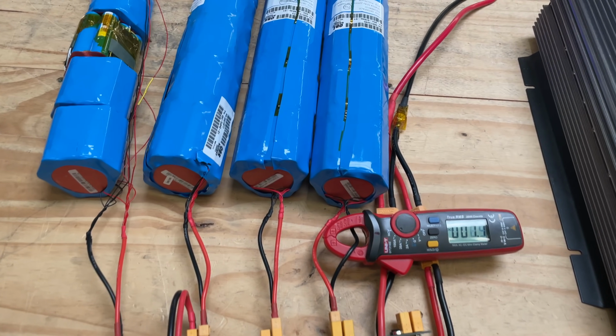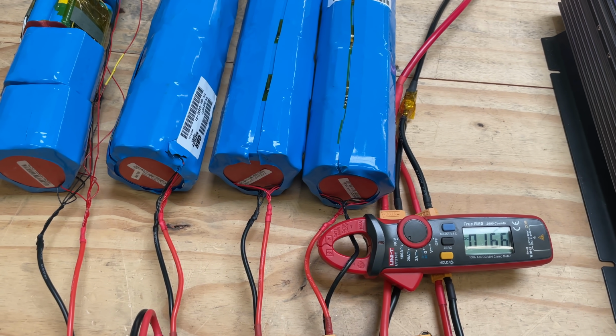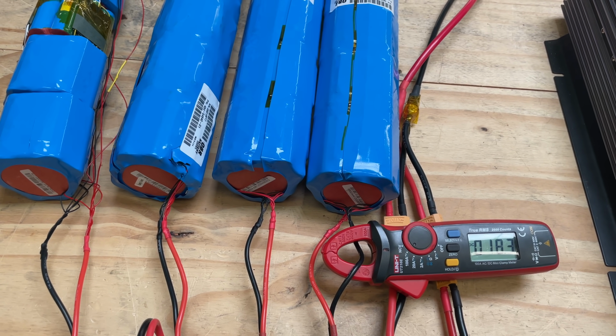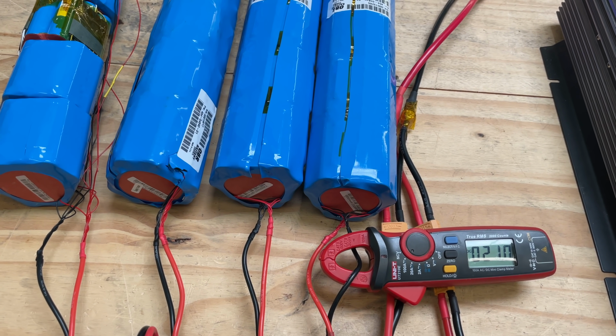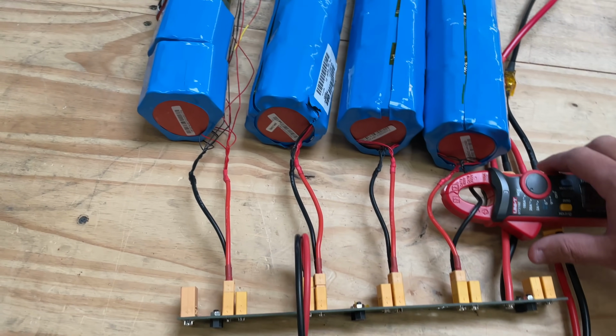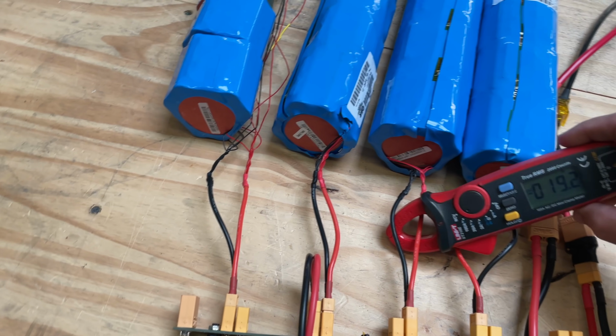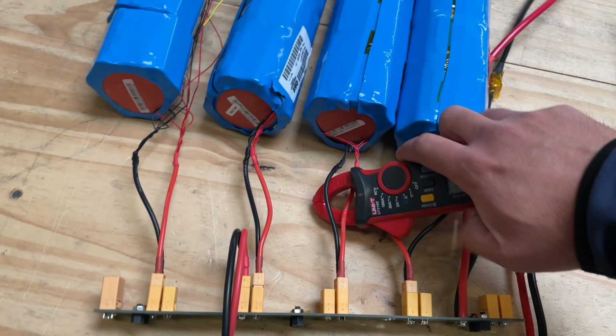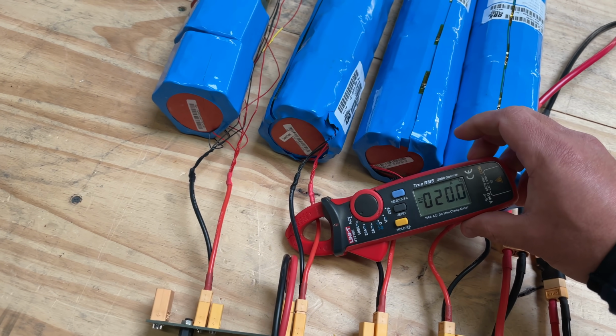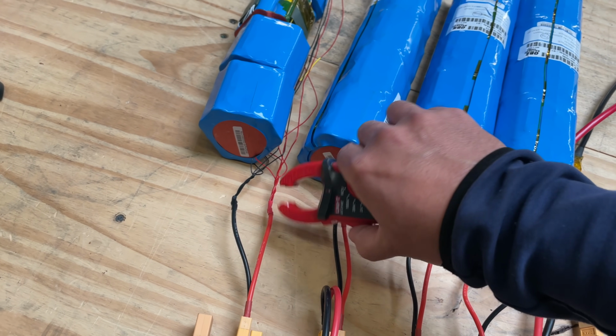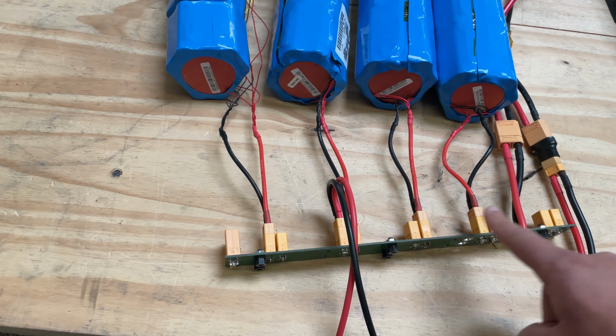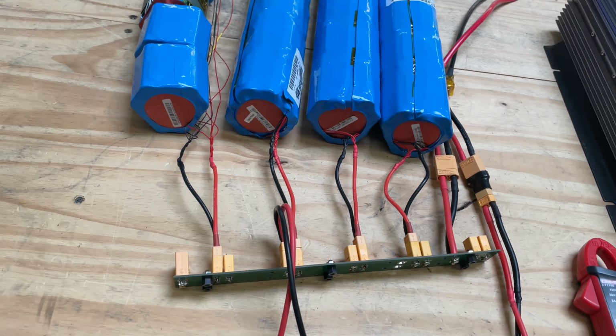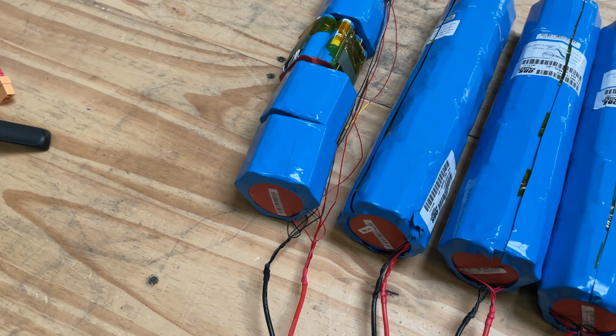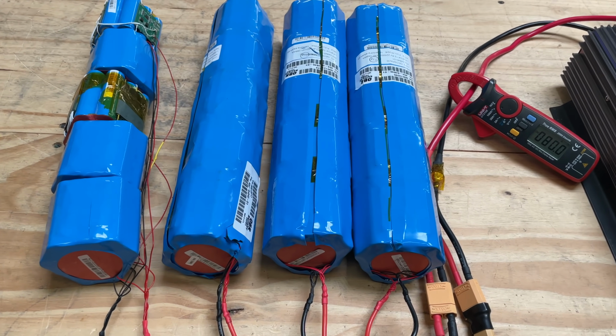So here we go, we're going to add, there we go, 10. So there's about 21 on that one. Let's see if this is well distributed. It's not - this is 19, this is 20, this is 19. Okay, so 2 of these packs are pushing about 1 amp more because of where the power is being taken off of this power strip. The overall into the inverter is 80, so we're exactly around 80.